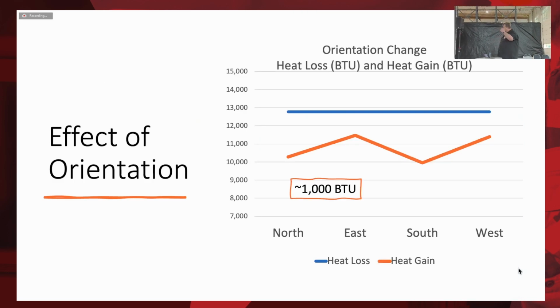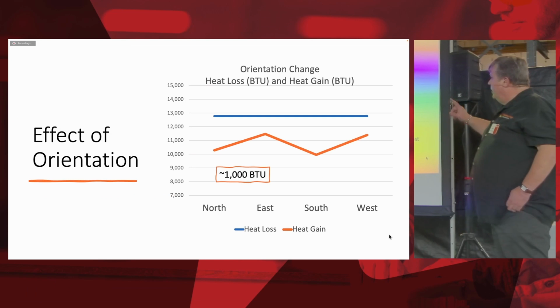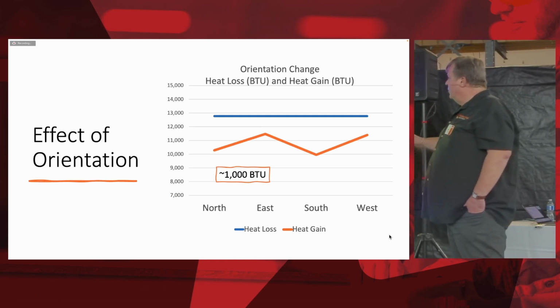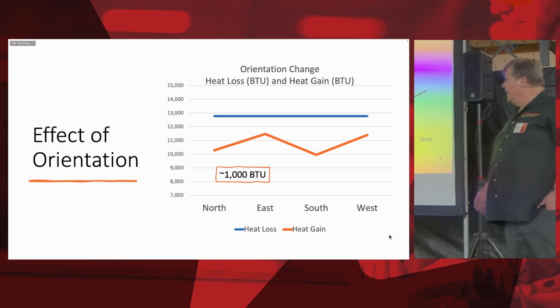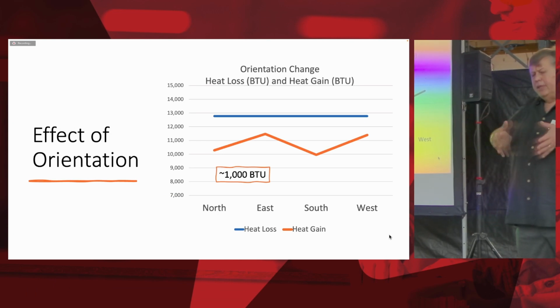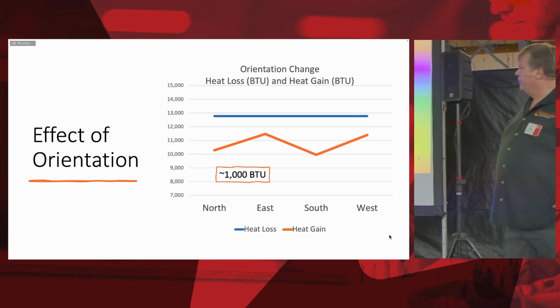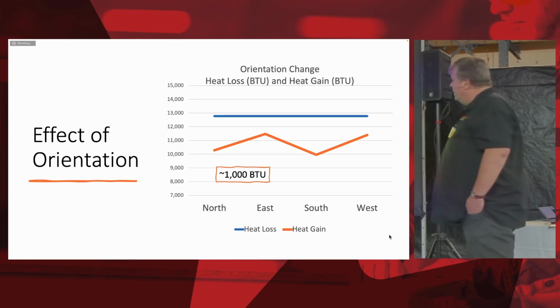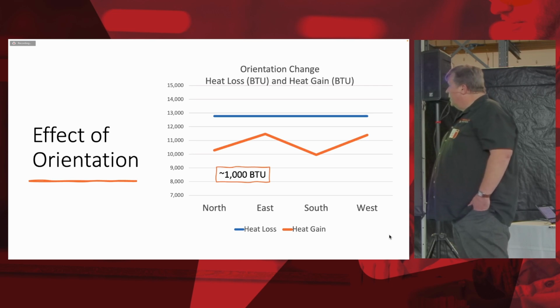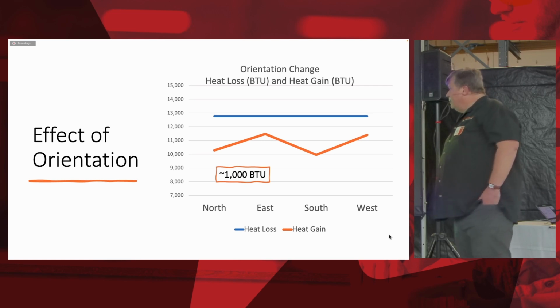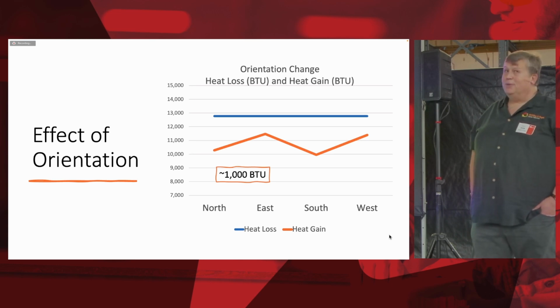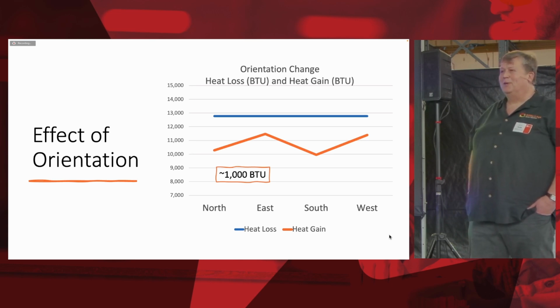Let's wind up here quickly. What does this look like when you run F280s? We've done this for tons of archetypes, for every zone up to 7B. Here's the effect of that cabin's location facing north, east, south, or west. I'm talking about the main glazed, big doors, big room facing down to the river on the south elevation. Based on the window spec on this project, we only really get a variance of about 1,000 BTU, and mind you, we only have a net 12,000 BTU heating and cooling load on this thing.